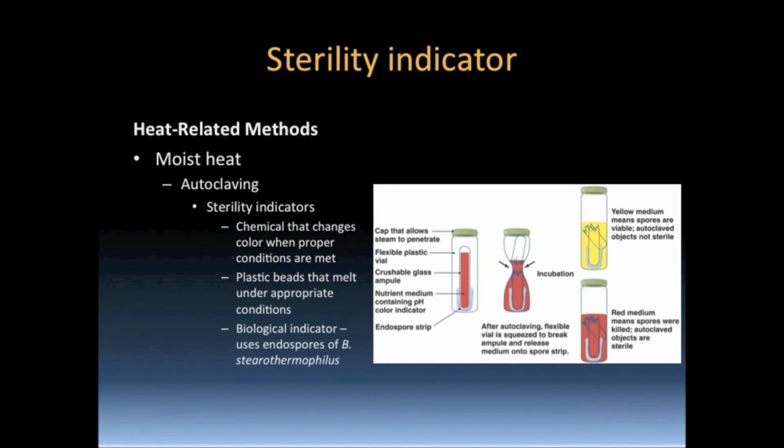Items sterilized using autoclaves must be able to tolerate high heat and moisture. Autoclaves are used to sterilize laboratory media and glassware, metallic instruments, and heat-resistant plastics. Items that are heat labile are destroyed in the autoclave. Therefore, if they are to be used again, autoclaving is not an option. The autoclave cannot be utilized to sterilize powders, as the steam would ruin such items, or substances that repel moisture such as oils and waxes.